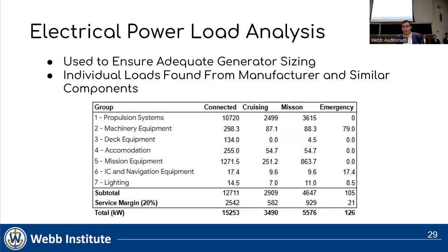The NSV electrical system was developed by breaking down and estimating various categories of loads. Load factors for cruising, mission, and emergency conditions were assigned to all the loads. Mission operations are calculated to be the most power-intensive conditions at about 5,600 kilowatts. This is because of the pumps needed to transport nuclear fuel and cooling water to and from an adjacent vessel.